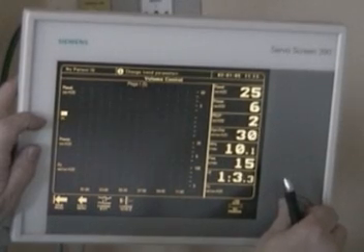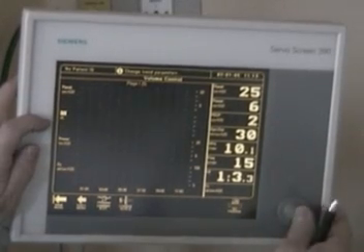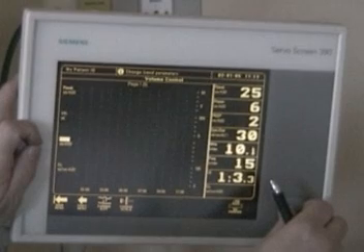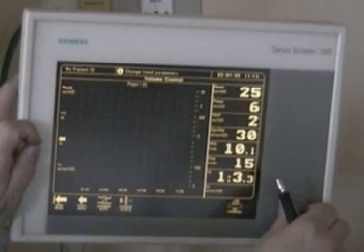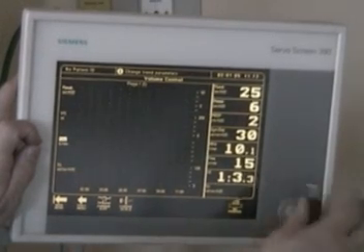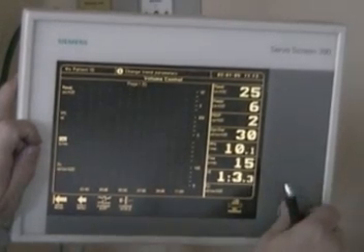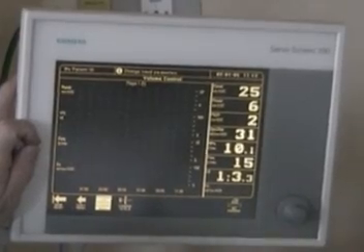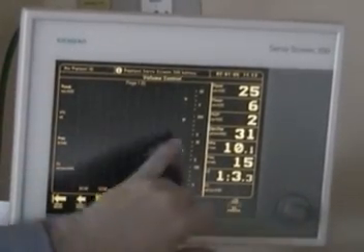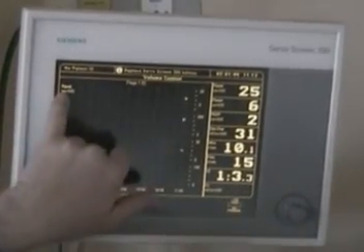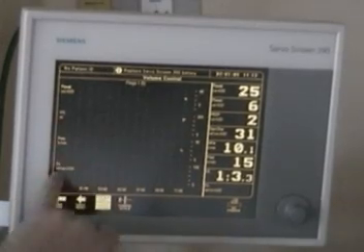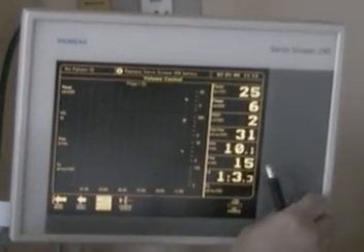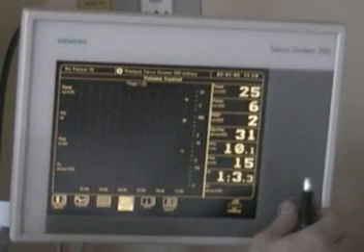Let's change this to volume — tidal volume inspired — and we'll change mean to frequency. Then we can go back and get different information: now we're getting peak tidal volume and frequency. That gives you some idea of what you can do with this digital display.